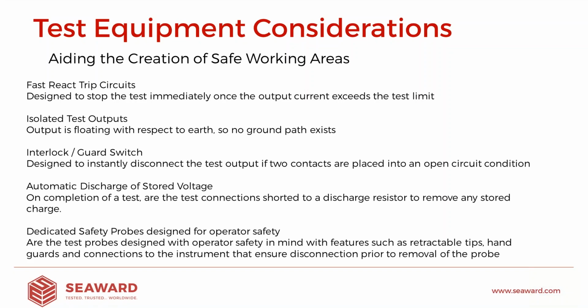So as soon as the test is finished, the HAL unit or our test unit switch over to a discharge resistor that removes any stored charge. So by the time the operator comes to pick it up, the unit should be safe for contact. And then finally, we spoke about safety probes a little bit earlier on, making sure that they've got things like retractable tips. Again, make sure the probes you are going to use are specifically designed for that purpose.